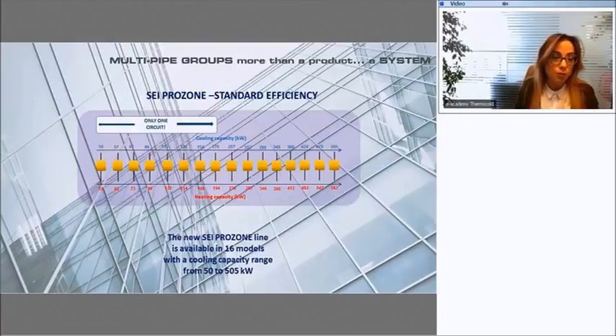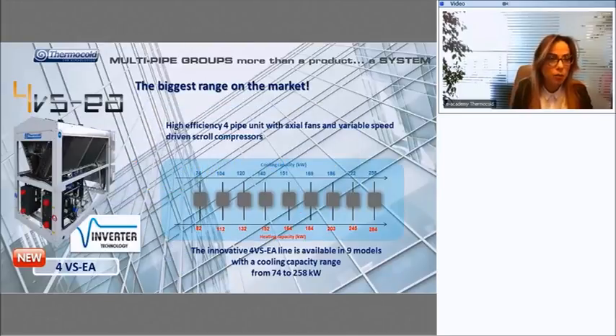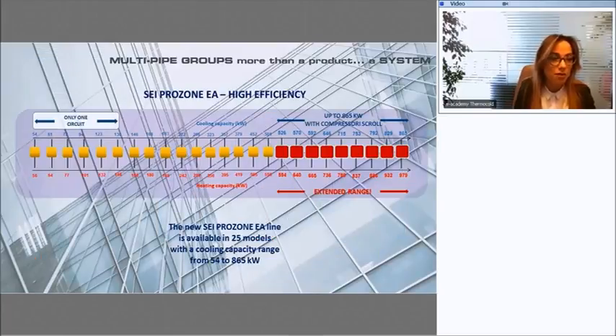Here we have the heating operating mode, the maximum outlet water temperature +60 and minimum outdoor air temperature -16 for the QUATTRO PROZONE and -18 for the QUATTRO PROZONE EA. In both cases, the unit is able to produce +35 of outlet water temperature.